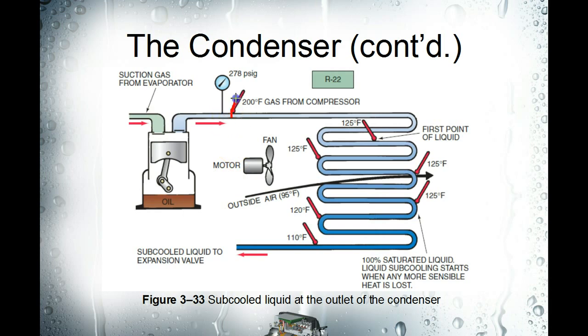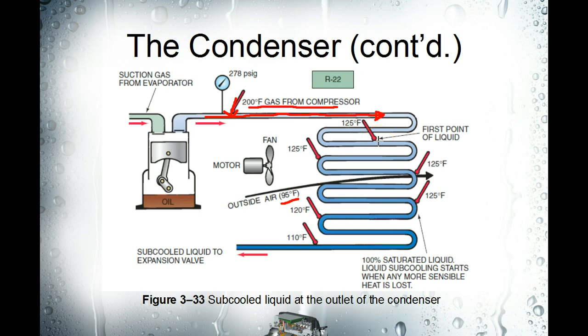At the outlet of the compressor, if you could measure it, you would read 200 degrees right on that refrigeration line. As refrigerant exits the compressor and enters the condensing coil of the condensing unit, it is in the state of high pressure, high temperature gas. What will happen is the fan motor blows 95 degree air across the hot vapor, and at a certain point in the condensing coil that high pressure high temperature gas will start to release its latent heat.